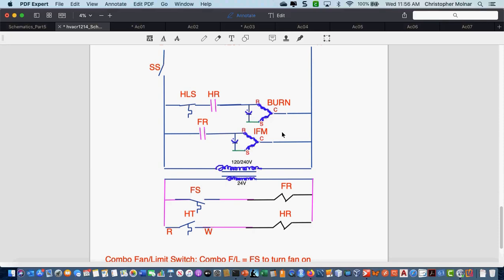Now, is the limit switch a manual reset safety? No. You are correct. It is not a manual reset. Why? It shuts off on temperature. Well, it shuts off on temperature, but why don't I need to have someone press a button to turn it back on? Why don't I want somebody to press a button to turn it back on? Be wasting our time.